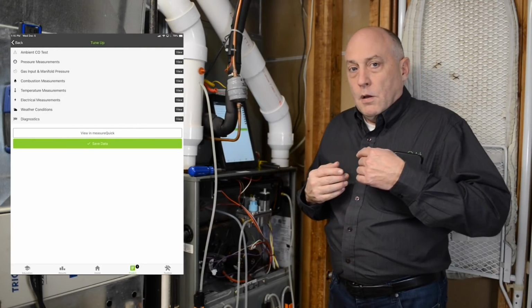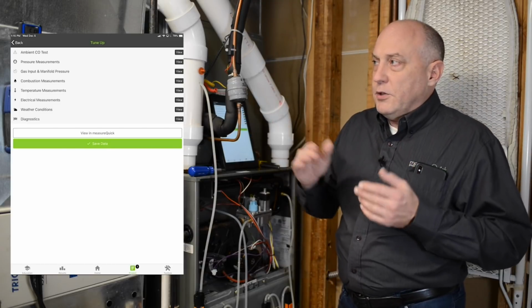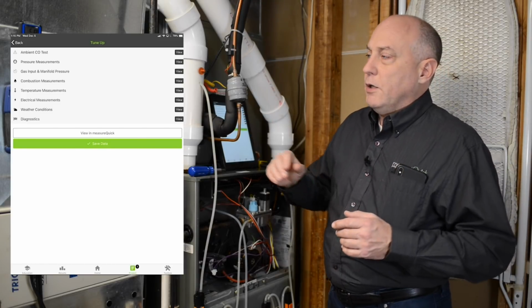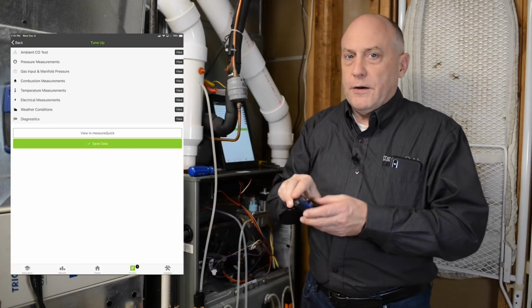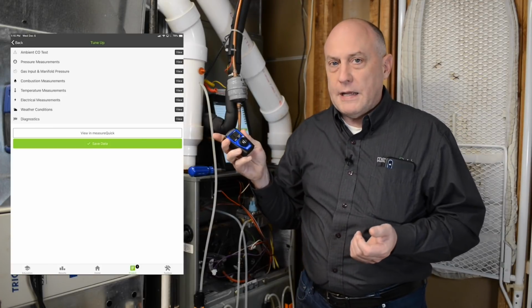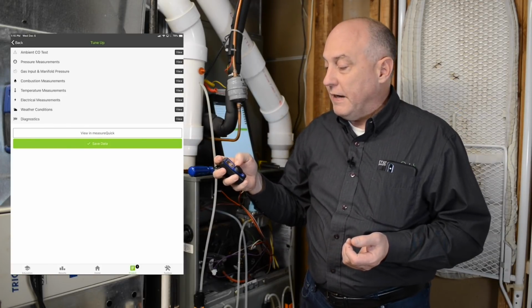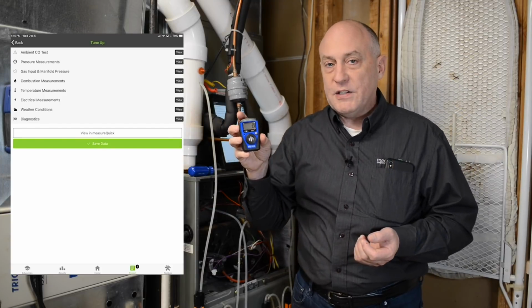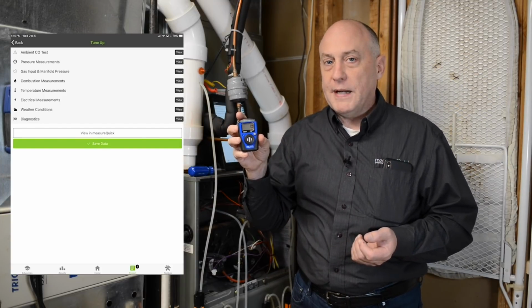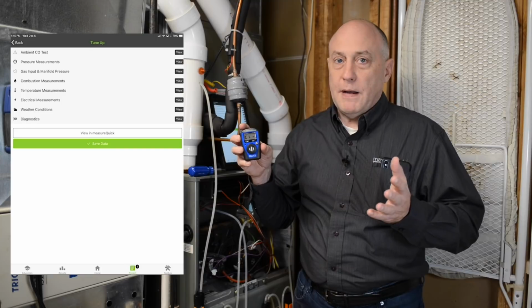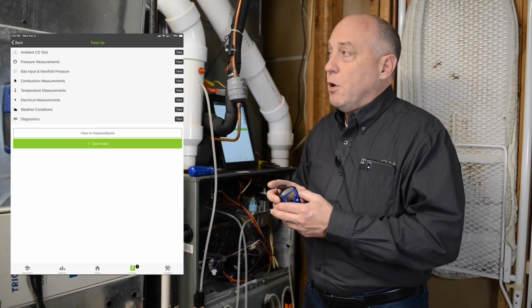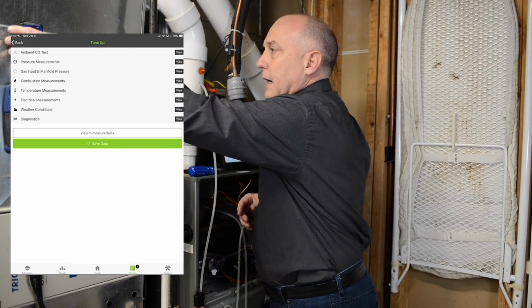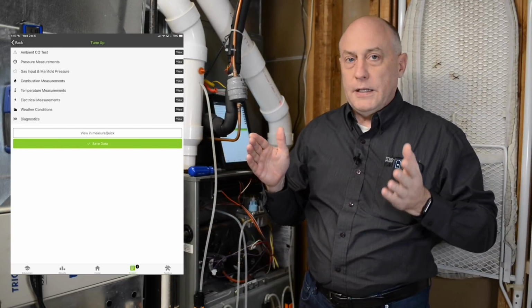Now, in the last video we showed how to use the AccuTools product. I do want to talk about the ambient CO meter we have in here. With an ambient CO meter, I'm constantly monitoring my CO. So if I hit a couple keys here, you can see that I have this at 0 parts per million of carbon monoxide. So I don't have anything to worry about as far as CO in the space, and I'm okay to set my analyzer up and just run it in the room here.